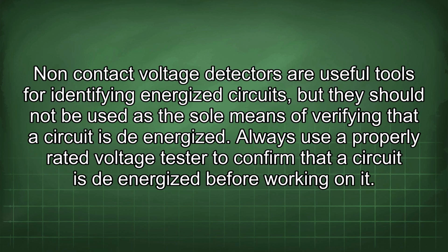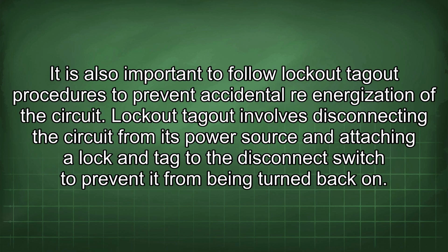Non-contact voltage detectors are useful tools for identifying energized circuits, but they should not be used as the sole means of verifying that a circuit is de-energized. Always use a properly rated voltage tester to confirm that a circuit is de-energized before working on it. It is also important to follow lockout-tagout procedures to prevent accidental re-energization of the circuit. Lockout-tagout involves disconnecting the circuit from its power source and attaching a lock and tag to the disconnect switch to prevent it from being turned back on.